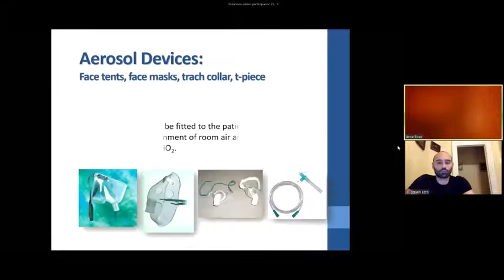Now, what you're going to see in the hospital is going to be this Venturi mask. The Venturi mask is going to give you anywhere from 24 to 50% oxygen, and it takes air from the environment, and it also brings in the oxygen support as well. You'll see down here, can you see that I'm pointing this out? Each one of those nozzles goes on the bottom here, and you see the blue color thing in the oxygen corrugated tubing. Each one of these has a different percentage of oxygen that you're going to see with a different liter flow. I don't remember off the top of my head. I always have to look at it.